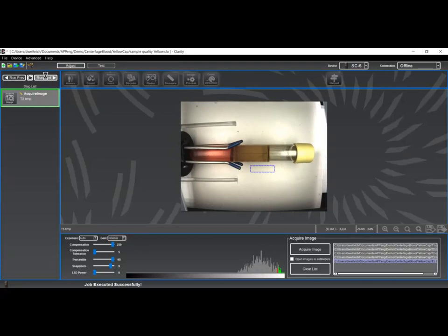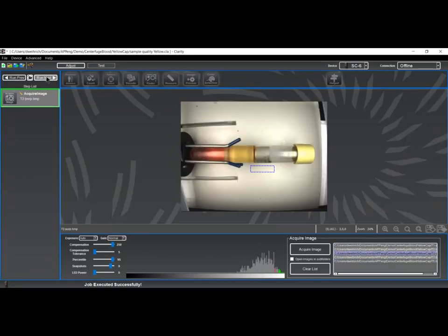For each of these samples, what is of interest and the areas to be measured are the color and purity of the serum section and the color of the red blood cell section. There's also measurement being done on the total volume, to guide machinery farther down in processing, maybe inserting a needle through the top that will be pulling a sample. It needs to know the height of the serum and of the red blood cell areas because it's going to go into one or the other to pull a sample out of the test tube.